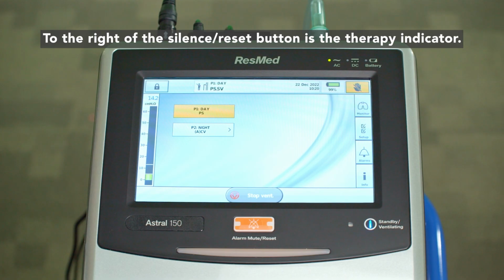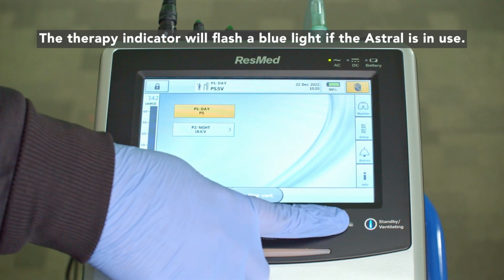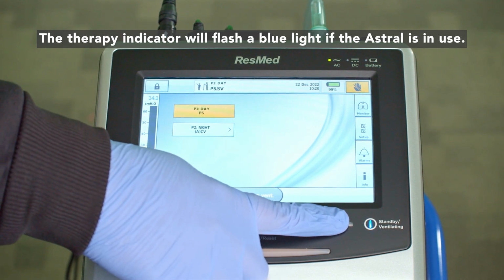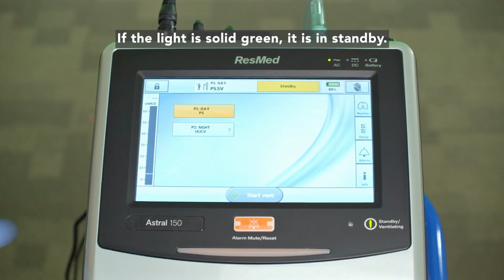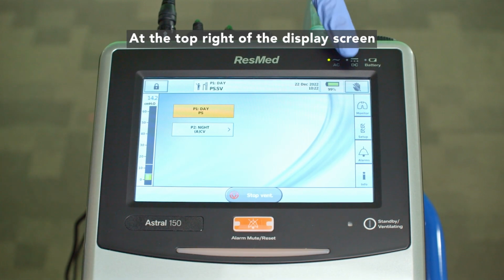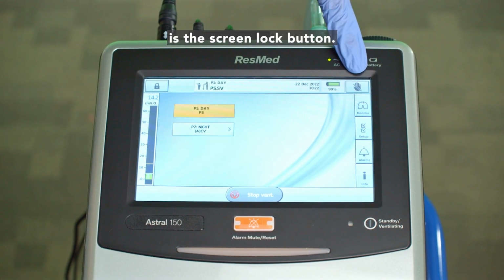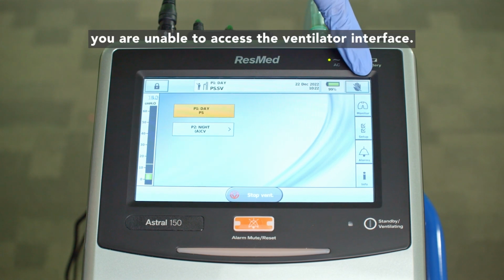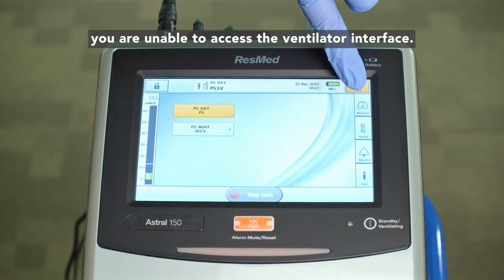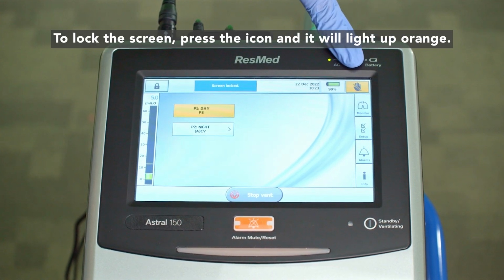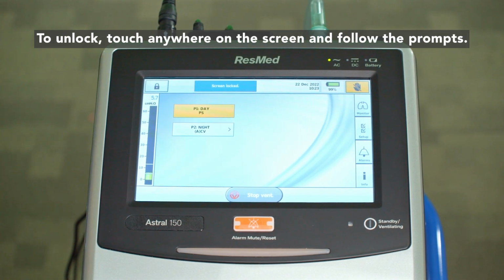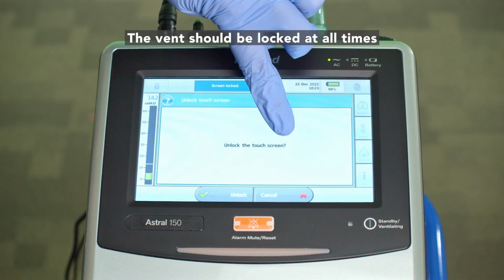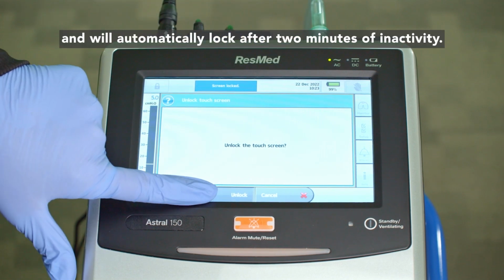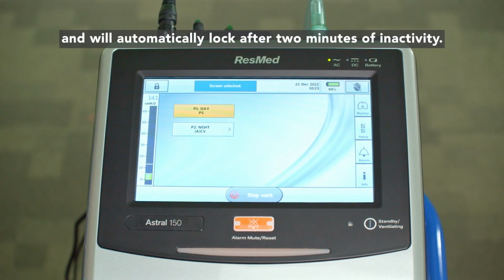To the right of the silence reset button is the therapy indicator. The therapy indicator will flash a blue light if the Astral is in use. If the light is solid green, it is in standby. At the top right of the display screen is a screen lock button. When the screen is locked, you are unable to access the ventilator interface. To lock the screen, press the icon and it will light up orange. To unlock, touch anywhere on the screen and follow the prompts. The vent should be locked at all times and will automatically lock after 2 minutes of inactivity.